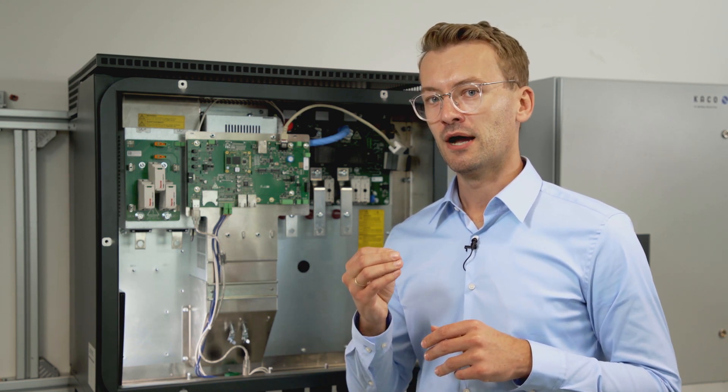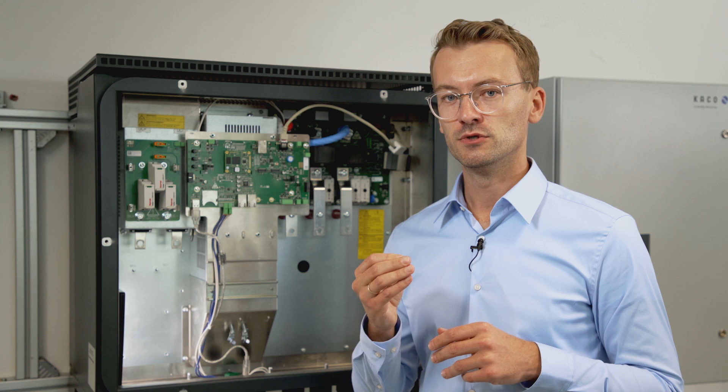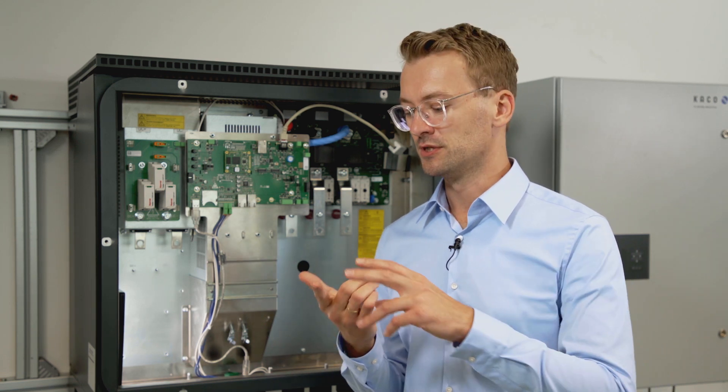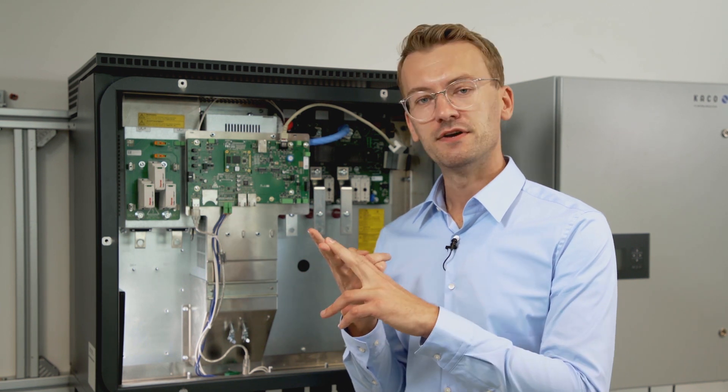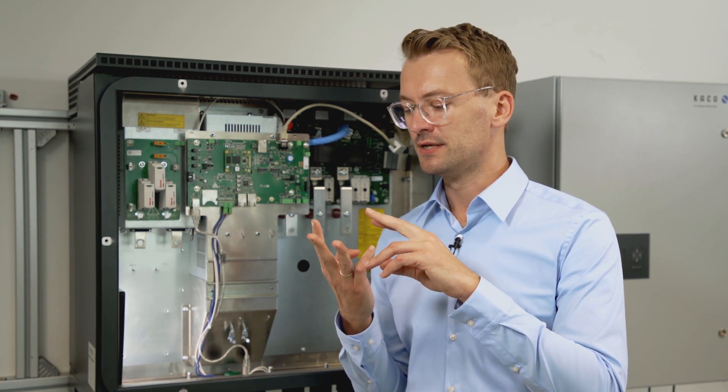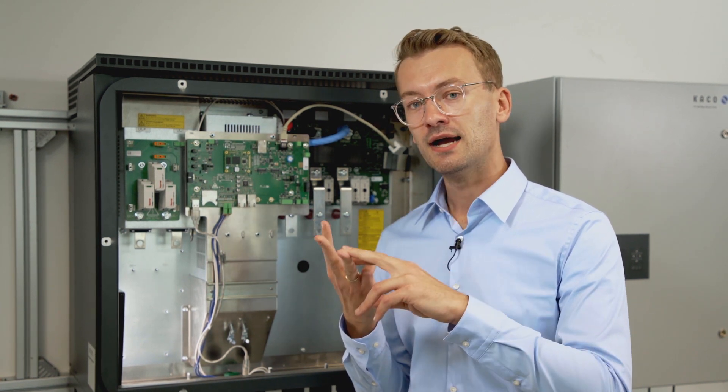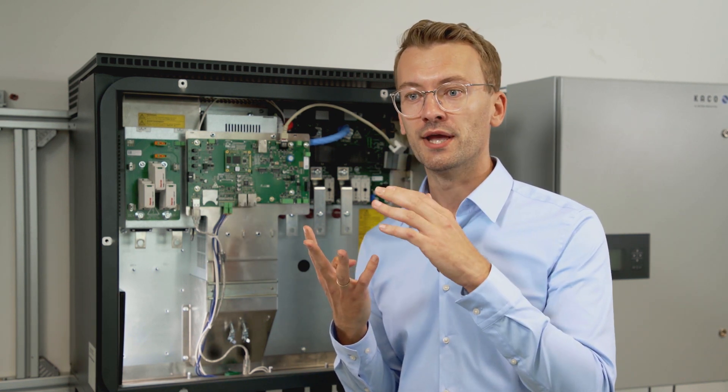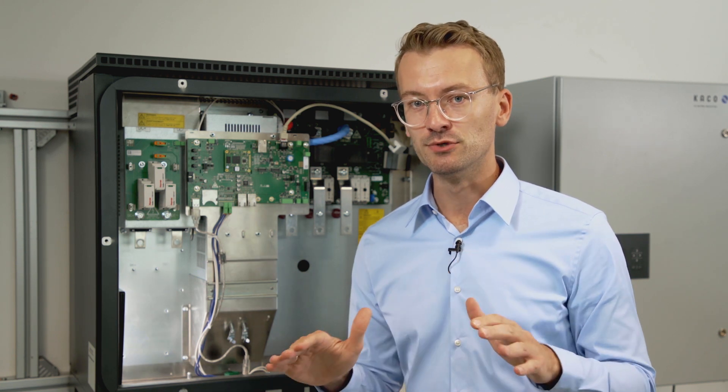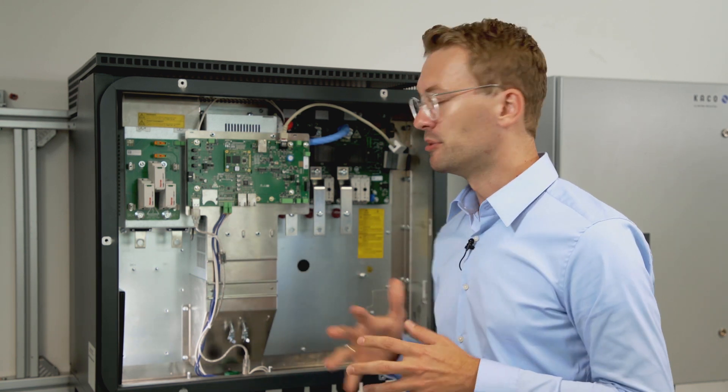When we're talking about your typical utility scale projects, where we're talking about the use of single axis trackers, bifacial modules, and in these times, a higher and higher rate of DC oversizing, where a multi-MPPT function is disabled anyway, a single MPPT inverter is the preferable choice.